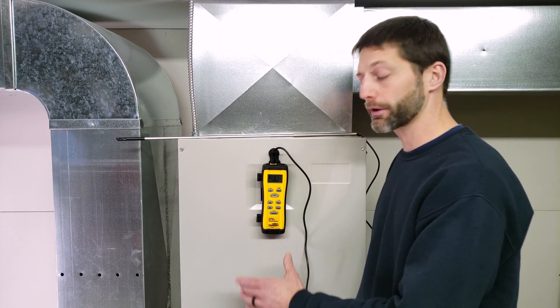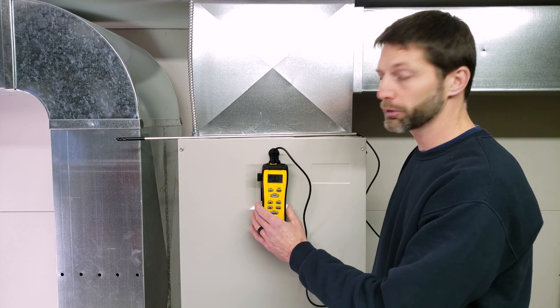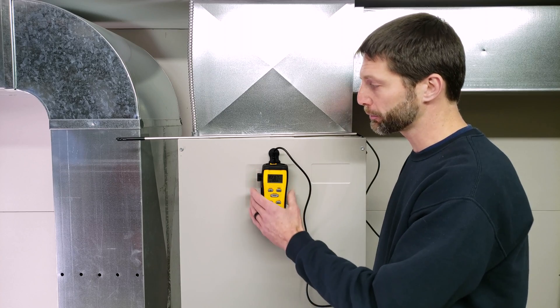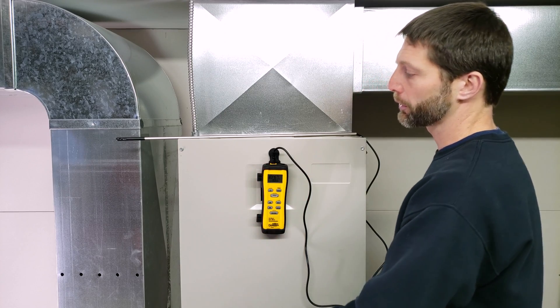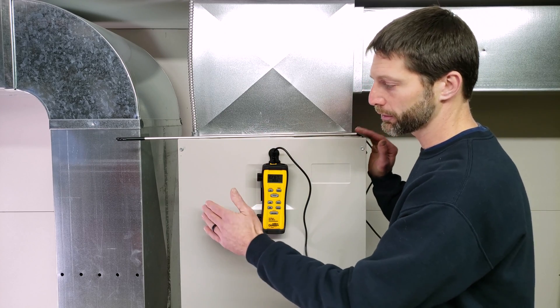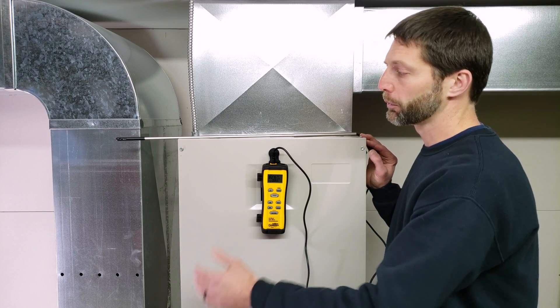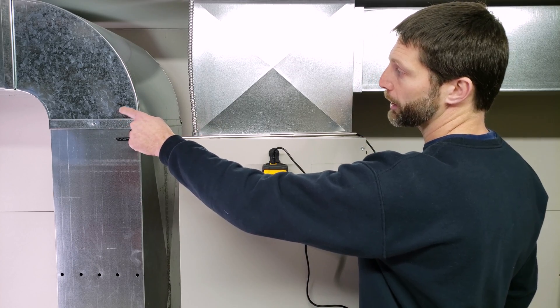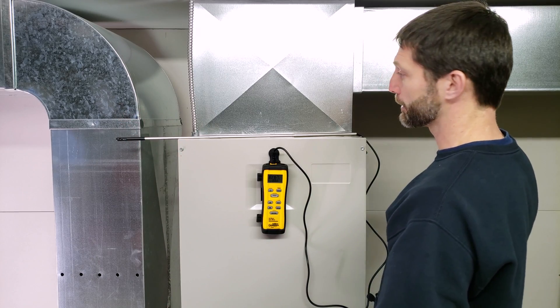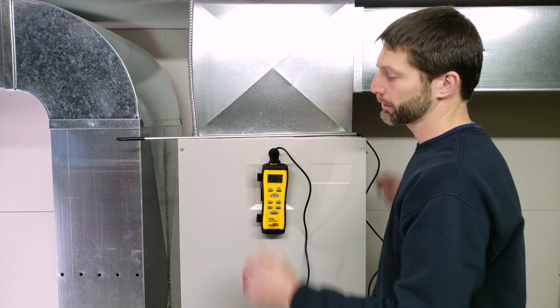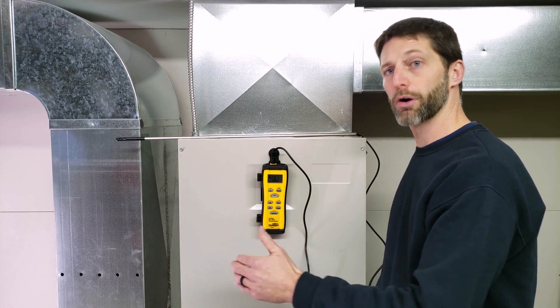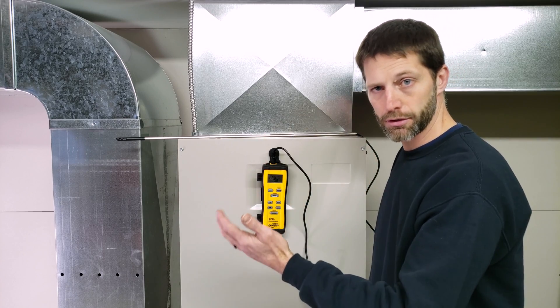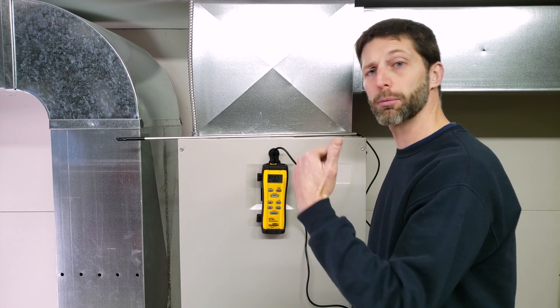Now that we measured our CFM with our in-duct anemometer, we're using the temp rise formula to verify this measurement. We'll temporarily shut the system off and take the cover off. We'll take an amperage reading on the electric strip heater and a temp rise between return duct and supply duct. Once our meter is in place, we'll turn the system on to do our calculations.